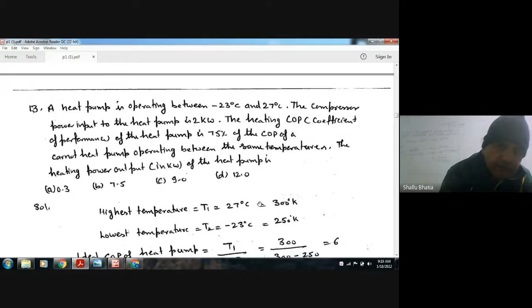Okay. So here the maximum temperature is 27 degrees Celsius, or in Kelvin it is 300 Kelvin, and the minimum temperature is minus 23 degrees Celsius, or in Kelvin it is 250 Kelvin. So the ideal COP of the heat pump is T1 by T1 minus T2, which is 6. The ideal COP of the Carnot cycle is 6. And the actual COP is 0.75 of this ideal COP, so this is 4.5. COP of the heat pump is nothing but the heating effect divided by the power input. The power input to the compressor is 2 kilowatt, and we have to determine the heating power. So heating effect is 4.5 times 2 kilowatts, so the answer is 9, option C.